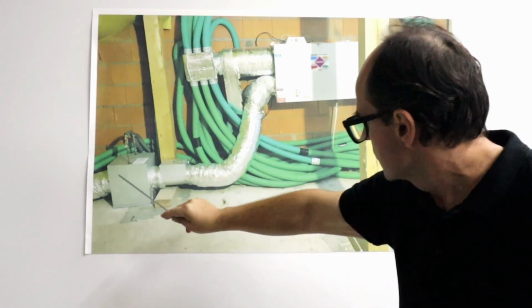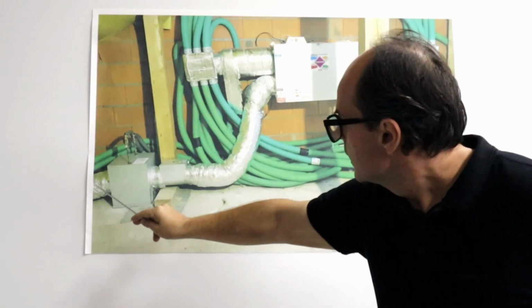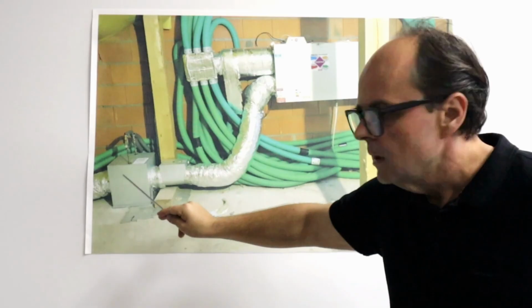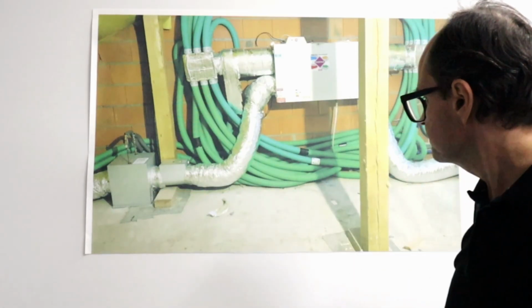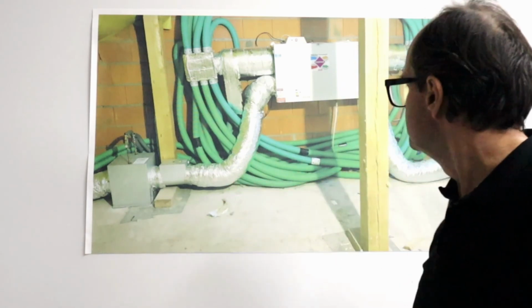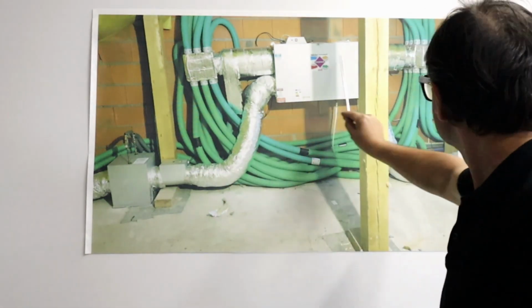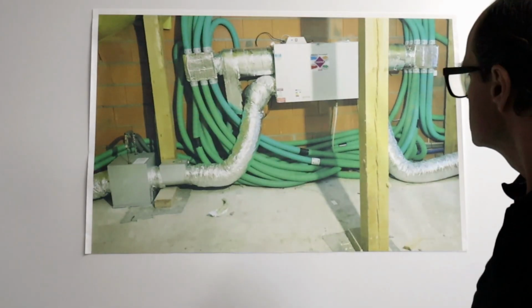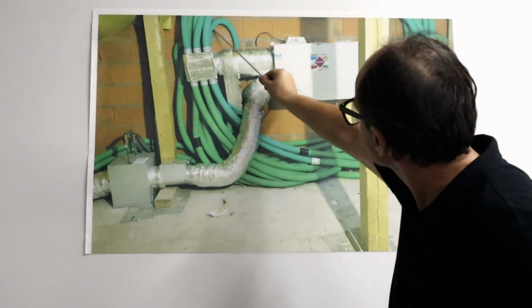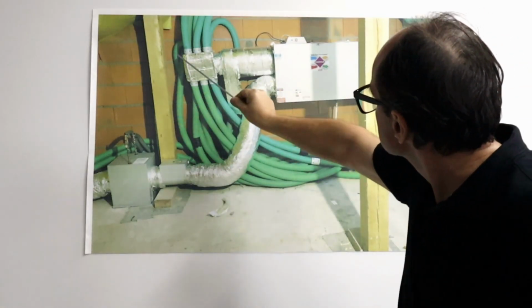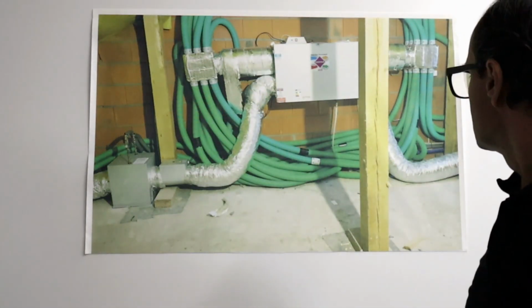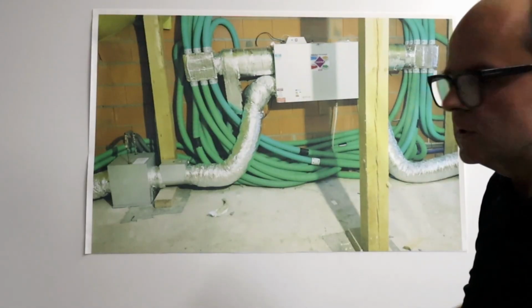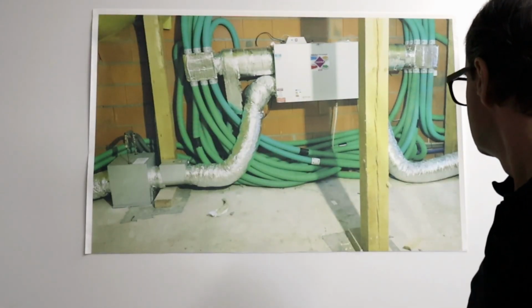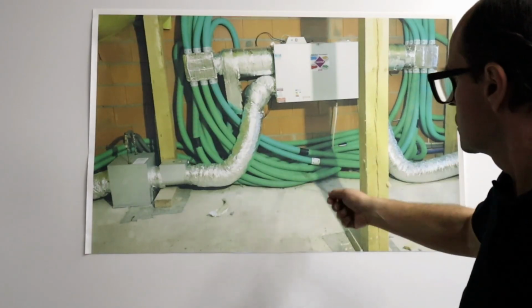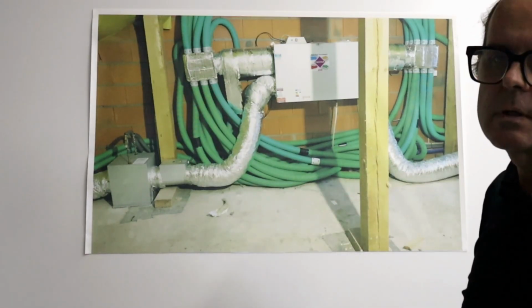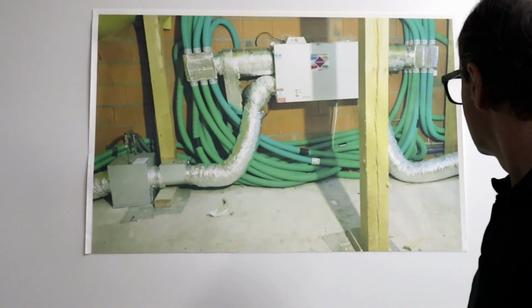If there was an electric heater here, it would warm the air up first. So this wouldn't freeze. As is, this will freeze immediately. We don't even know if this won't burn. Everything here along with these flows is selected in such a way that air probably won't reach, because the sections here are long bent sections like here, here and here. The distances here are around 20 meters. Air won't get to where it needs to go. Zero efficiency. In my opinion, it's a complete waste. I don't know how much the labor and the materials cost, but it's all wasted down the drain.